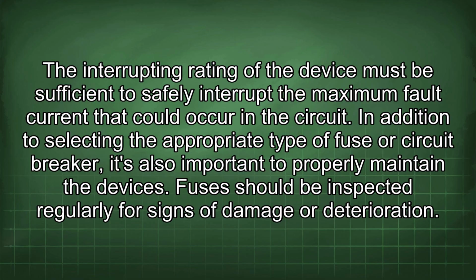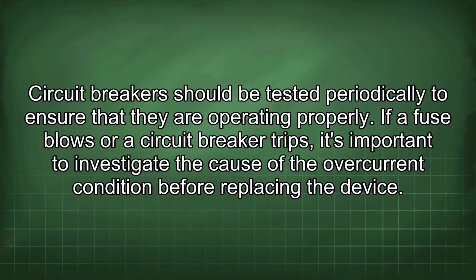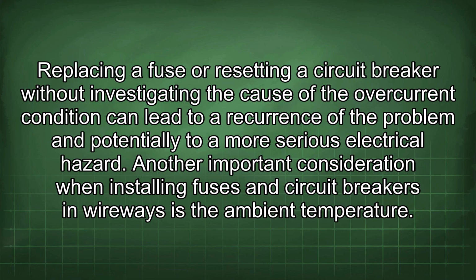the devices. Fuses should be inspected regularly for signs of damage or deterioration. Circuit breakers should be tested periodically to ensure that they are operating properly. If a fuse blows or a circuit breaker trips, it's important to investigate the cause of the overcurrent condition before replacing the device. Replacing a fuse or resetting a circuit breaker without investigating the cause of the overcurrent condition can lead to a recurrence of the problem and potentially to a more serious electrical hazard.